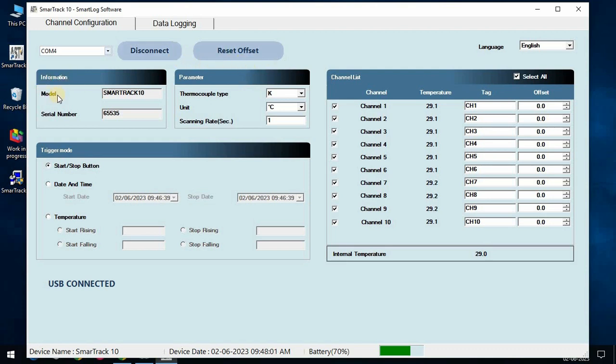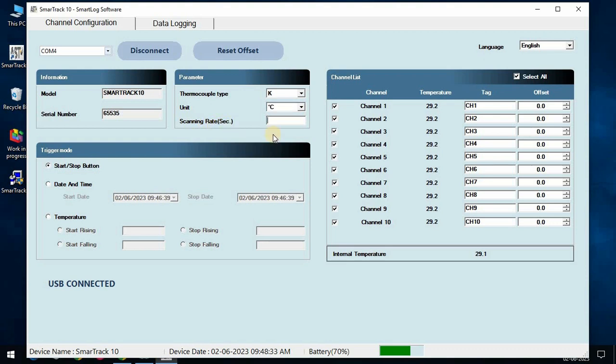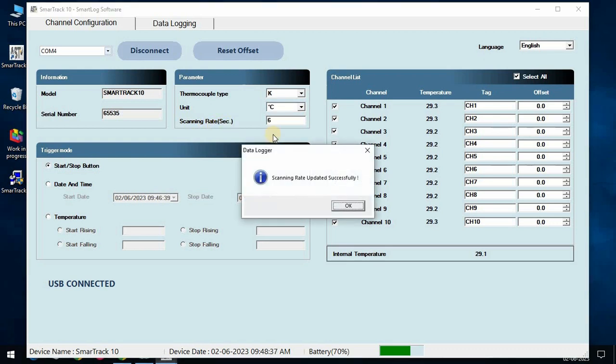Information tab shows the data logger name with its serial number. Parameter tab allows to choose thermocouple type, temperature unit, and the scanning rate per channel. After changing the scanning rate, please press the enter button to save the entry.